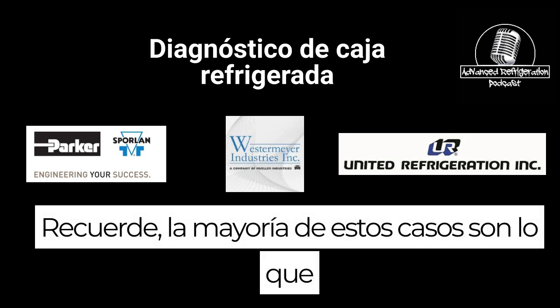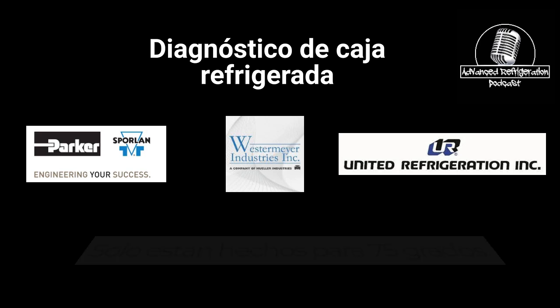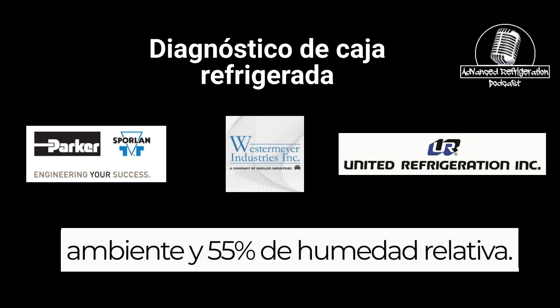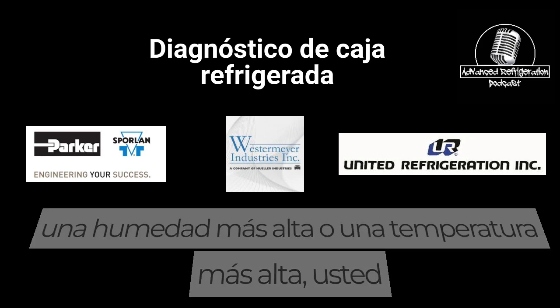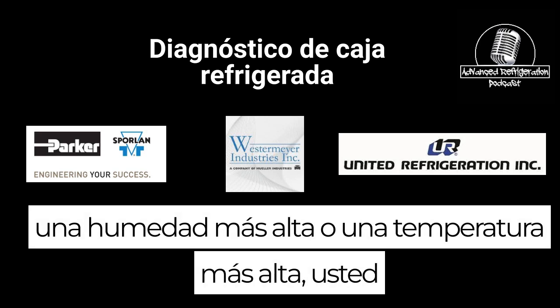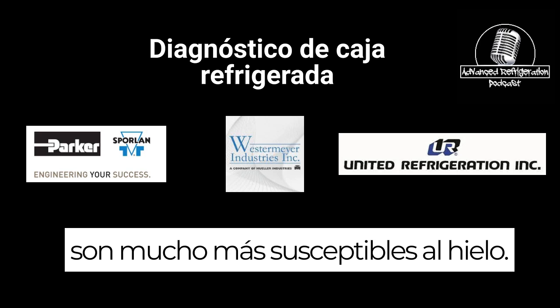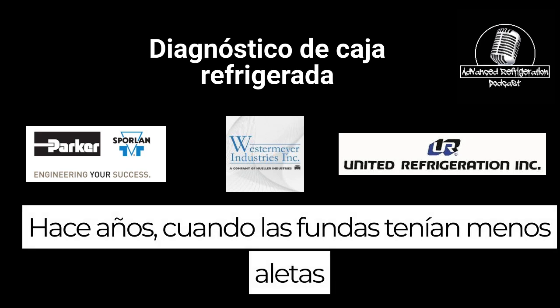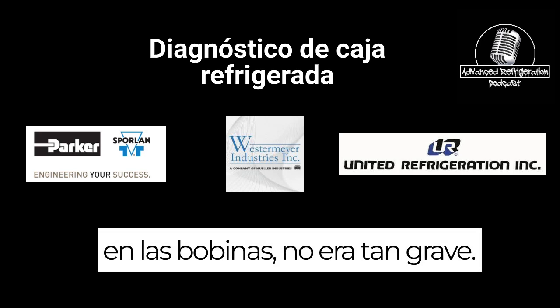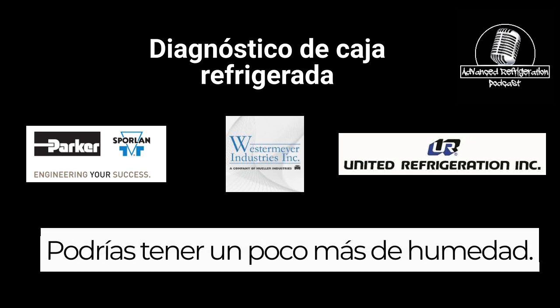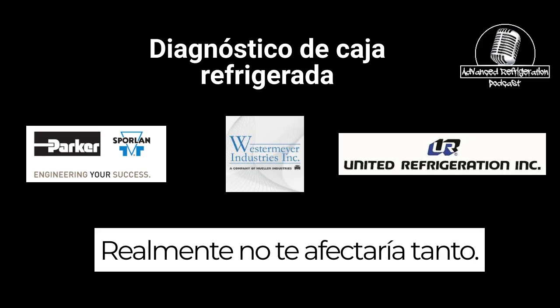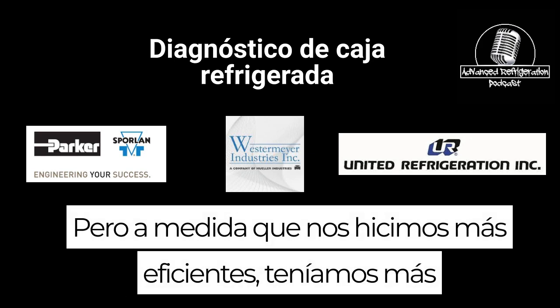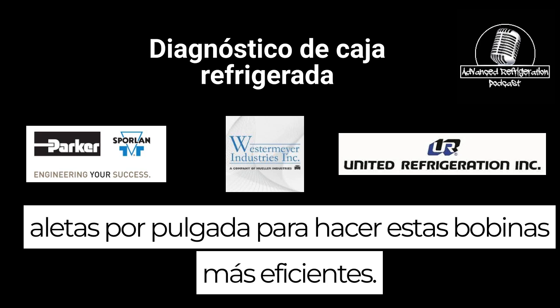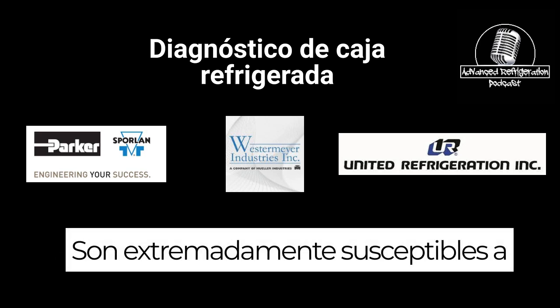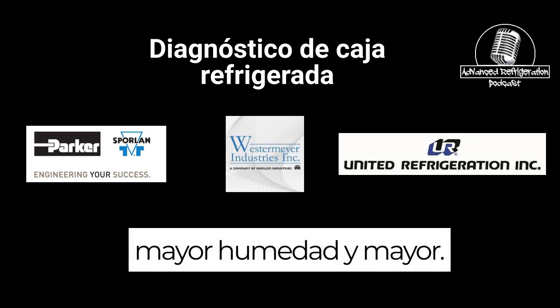Remember, most of these cases are what they refer to as type 1 cases. They're only made for 75-degree ambient and 55% relative humidity. If either of those specs is higher, whether humidity or temperature, you are way more susceptible to ice up. Years ago, when the cases had fewer fins in the coils, it wasn't that severe. You could be a little bit higher in humidity and it really wouldn't affect you all that much. But as we got more efficient, we had more fins per inch to make these coils more efficient. They're extremely susceptible to higher humidity and higher temperature.